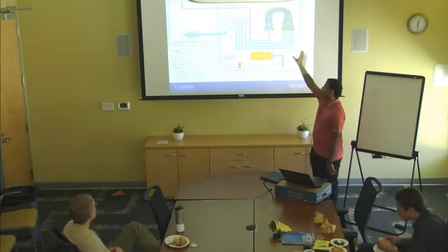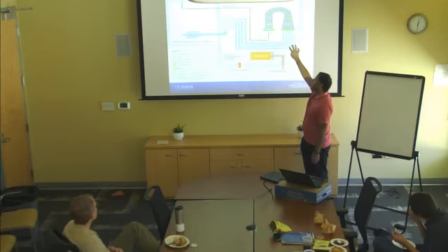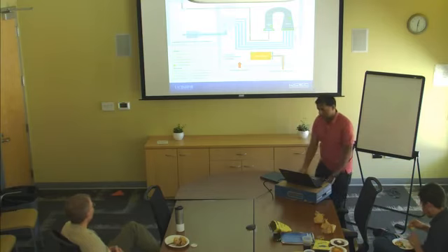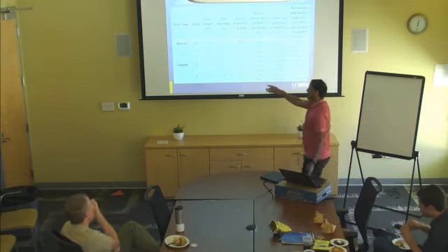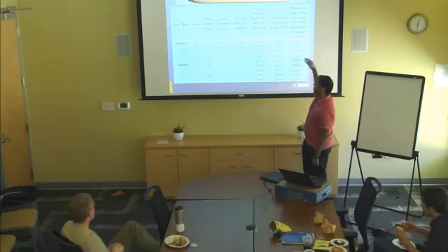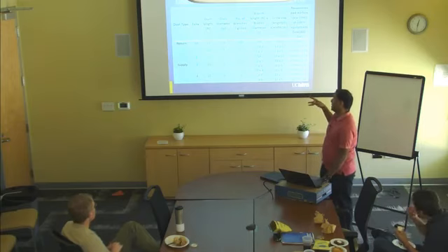So basically the air is being delivered to the grills through 4 branches, which are not necessarily equal in dimensions. You can see one duct is 25 feet long, whereas another duct is 12 feet long. They have different numbers of branches, and they carry different amounts of air. So that's a good representative duct to investigate how the distribution system efficiency is affected by the variation of these parameters.